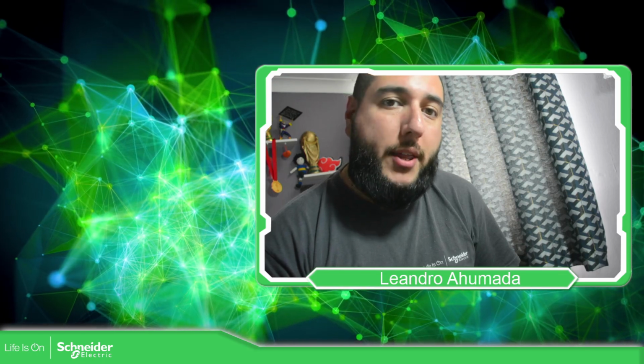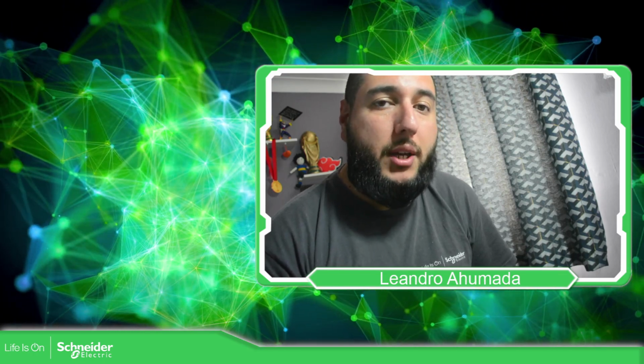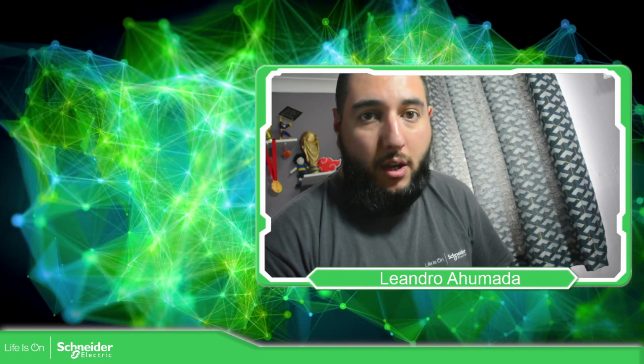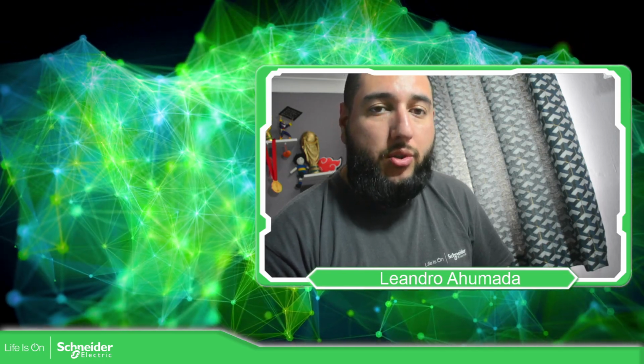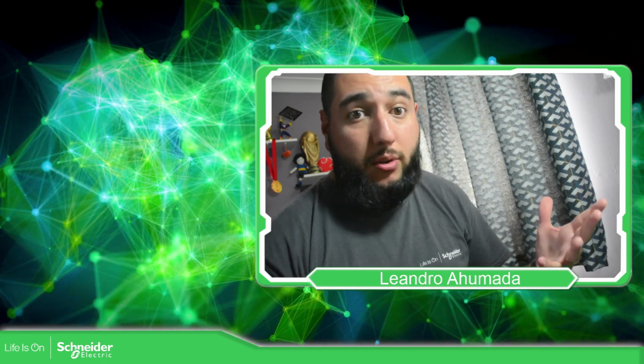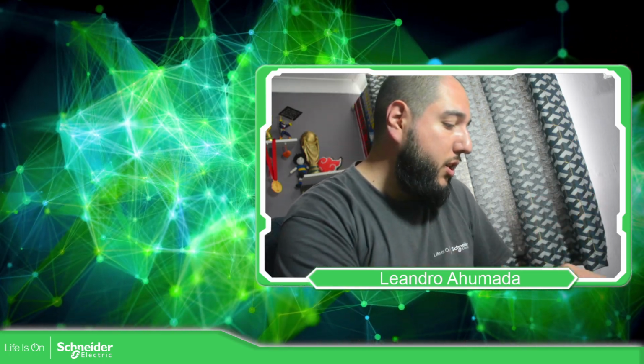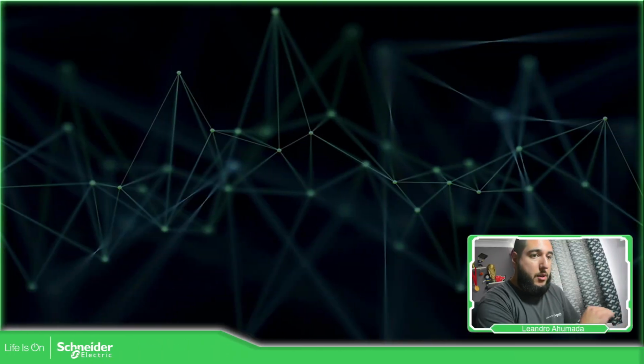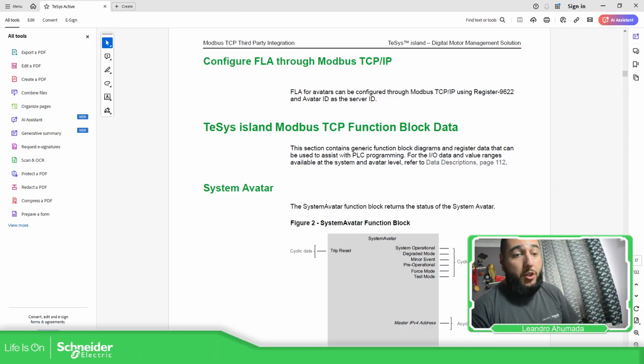I'm your host, Leandro Ahumada, and in this video what we're going to see is how we can change the FLA on the avatar selected using an HMI or any other software. So let's go to the manual first. In order to change the full load current, what we need to do is to check this register 9622. And it's important to know the IP address of the island and the avatar ID.